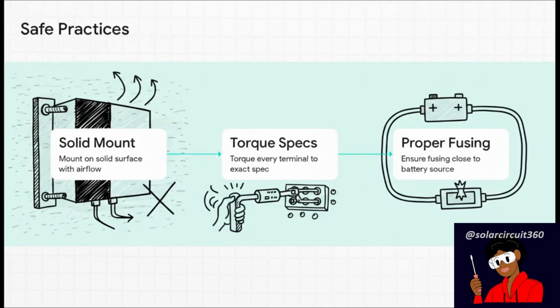Okay, so how do we actually solve this? How do we build it right? Well, here are the clear, absolutely non-negotiable safe engineering practices you have to bake into your design. Step 1. Mount that inverter on a totally solid surface with plenty of airflow clearance. It has to be a true vibration and heat anchor point, so absolutely no enclosed, unventilated closets. Step 2. Torque every single terminal to the exact manufacturer specification. Use a proper torque wrench. No guessing, no feels firm. And step 3. Ensure you have proper fusing as close to the battery source as physically possible. That's your frontline defense against those severe fault currents and arcs. Sticking to these steps ensures your system operates with a totally predictable current flow and a safely balanced discharge.